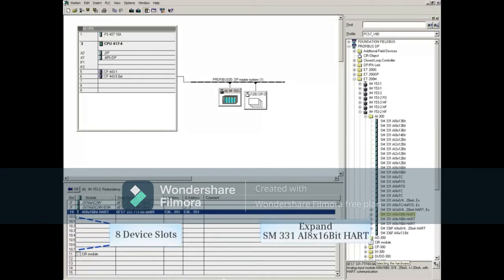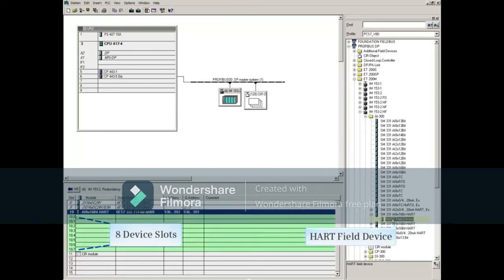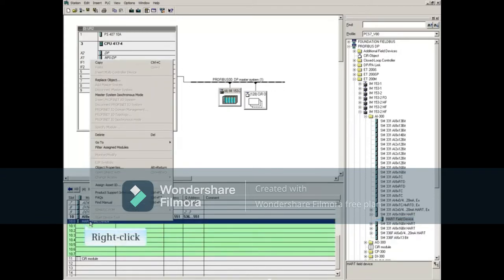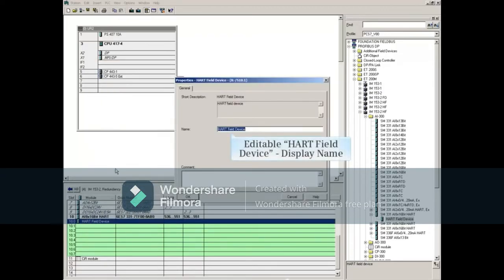Expand the SM331 AI 8X16bit HART module to show a representation of HART field devices. This HART field device object can now be placed in an available slot. Right-clicking and then opening its properties will allow you to give the HART field device object a more appropriate name.